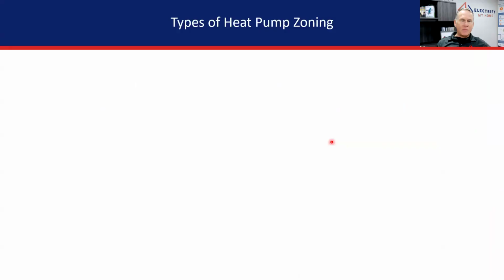So when it comes to heat pumps, it's a little bit different. If I've got a dual zone control system on, say, a two-stage air conditioner and a two-stage furnace, I can lay that system out where it's half the house for each stage, and I'm going to be at 60% operating capacity on low and 100% on high. We can make that work pretty easily. It's going to be okay. One zone closes, it pops back down into low stage. We've got some sort of control over it.